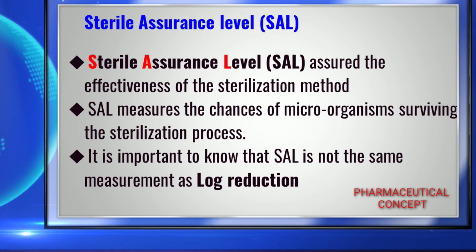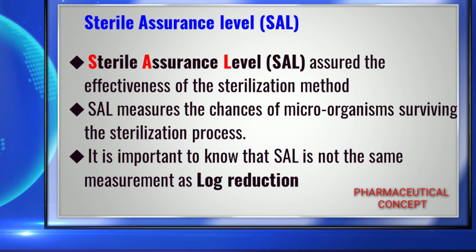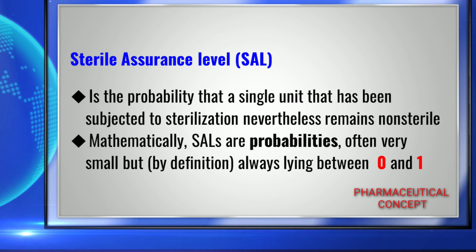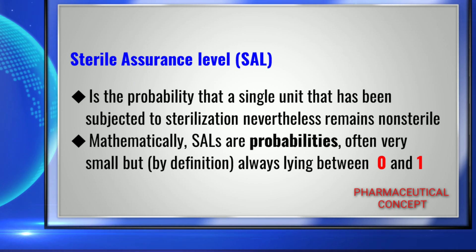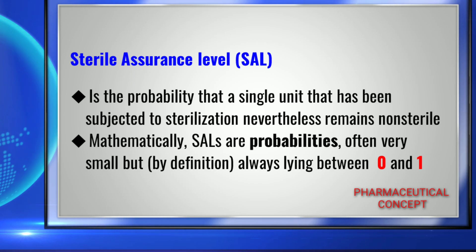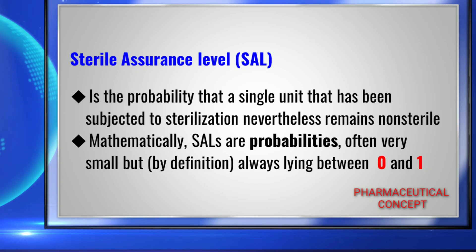It is important to know that SAL is not the same as measurement of log reduction. Sterility Assurance Level is the probability that a single unit, subjected to sterilization, nevertheless remains non-sterile. Mathematically, SALs are probabilities — often very small, but by definition always lying between 0 and 1.